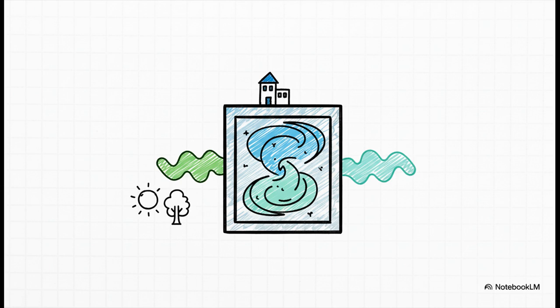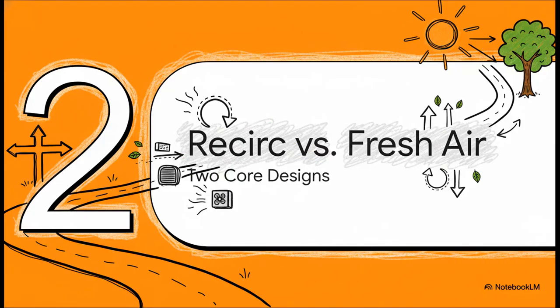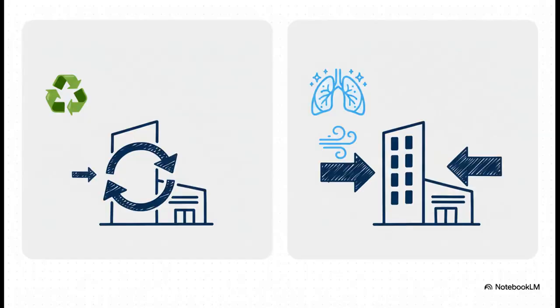This is where that blend happens, and it's a huge choice that impacts both energy use and air quality. And that one decision brings us to a fundamental fork in the road for AHU design. We're talking about the two core philosophies, recirculating air versus using 100% fresh air. This is a critical distinction that every engineer has to master, because it basically dictates the whole purpose and application of the unit.